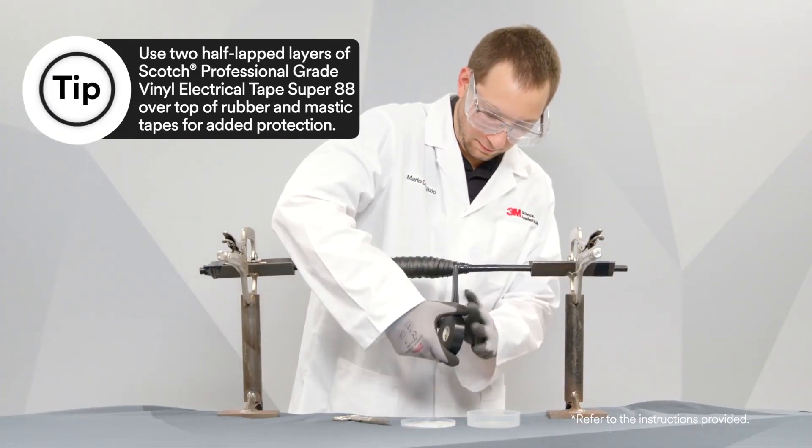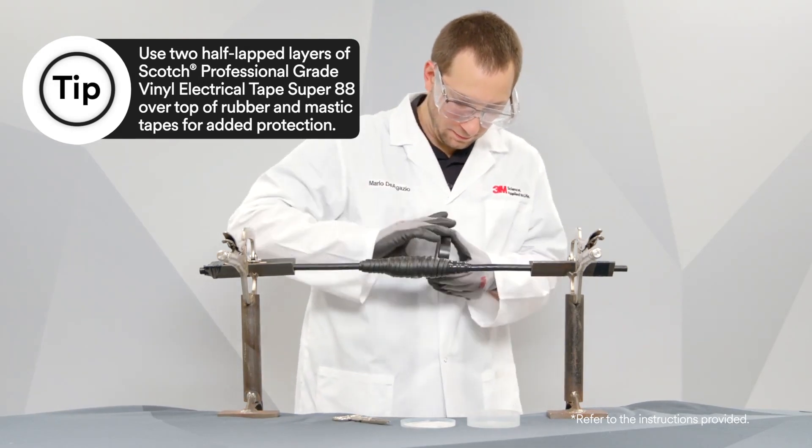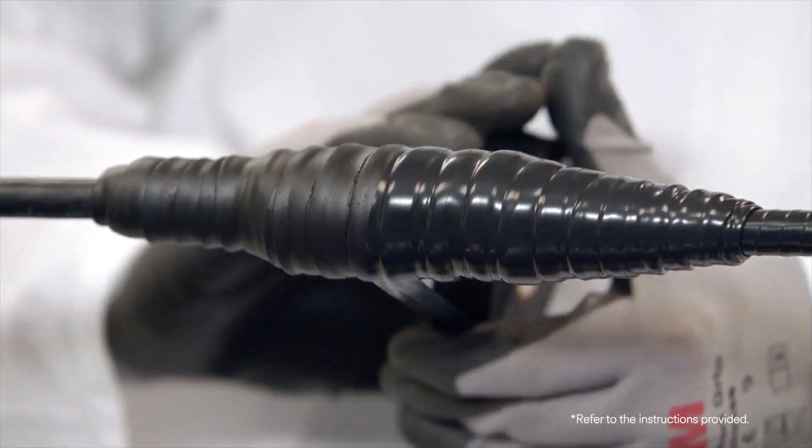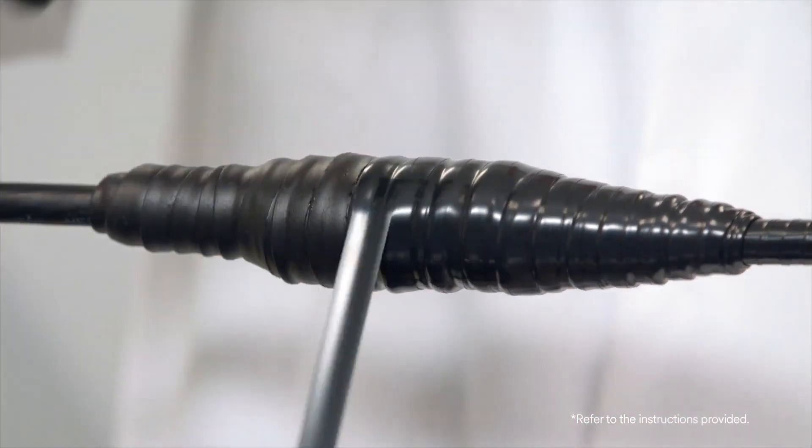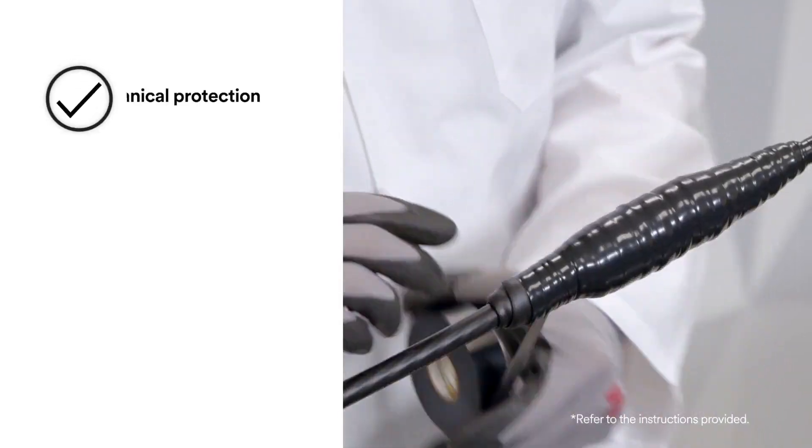One example is to use a minimum of two highly stretched, half-lapped layers of Scotch professional grade electrical tape Super 88 over top of mastic or rubber tapes to help provide extra mechanical protection, UV resistance, and to help create a better seal.